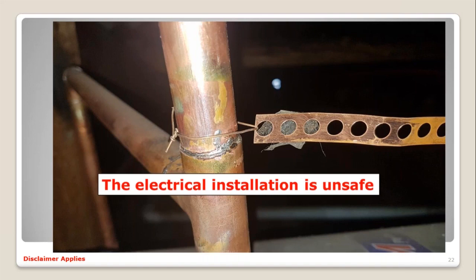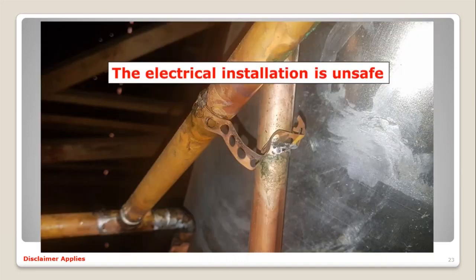So when you put your resistance tester between the two points, you will find that the resistance is much higher. When you connect the bonding strap around the pipe and take a resistance test again, you will find it's a little bit lower. So the resistance path we want to keep as low as possible. The same situation on this side. You can see that it was tacked or soldered on one end, but it could be not sufficient. To know if it's proper, you need to measure it. And again, you can't say if you don't have the instrumentation to measure it. So we would rather do the good practice and wrap it around and tighten it up.